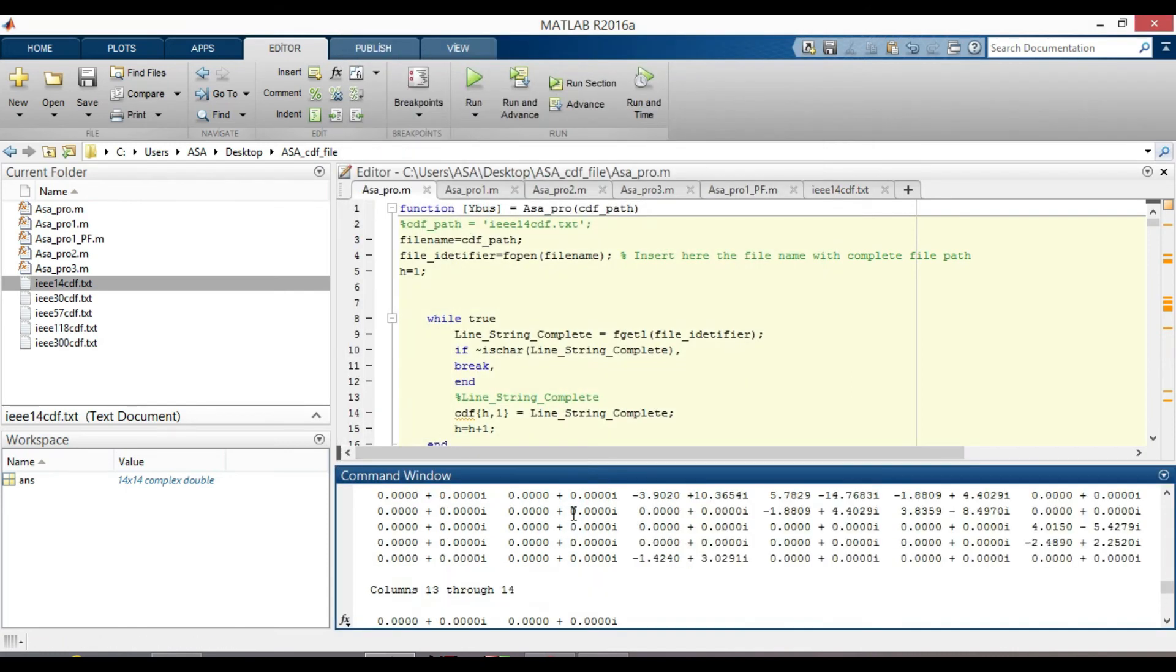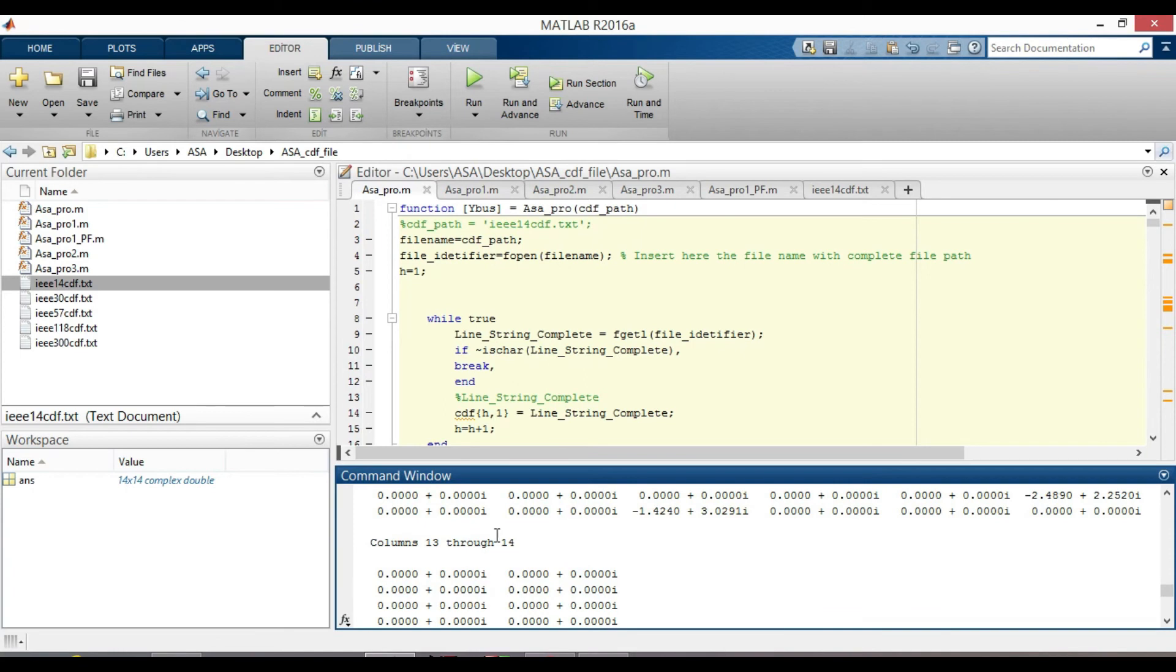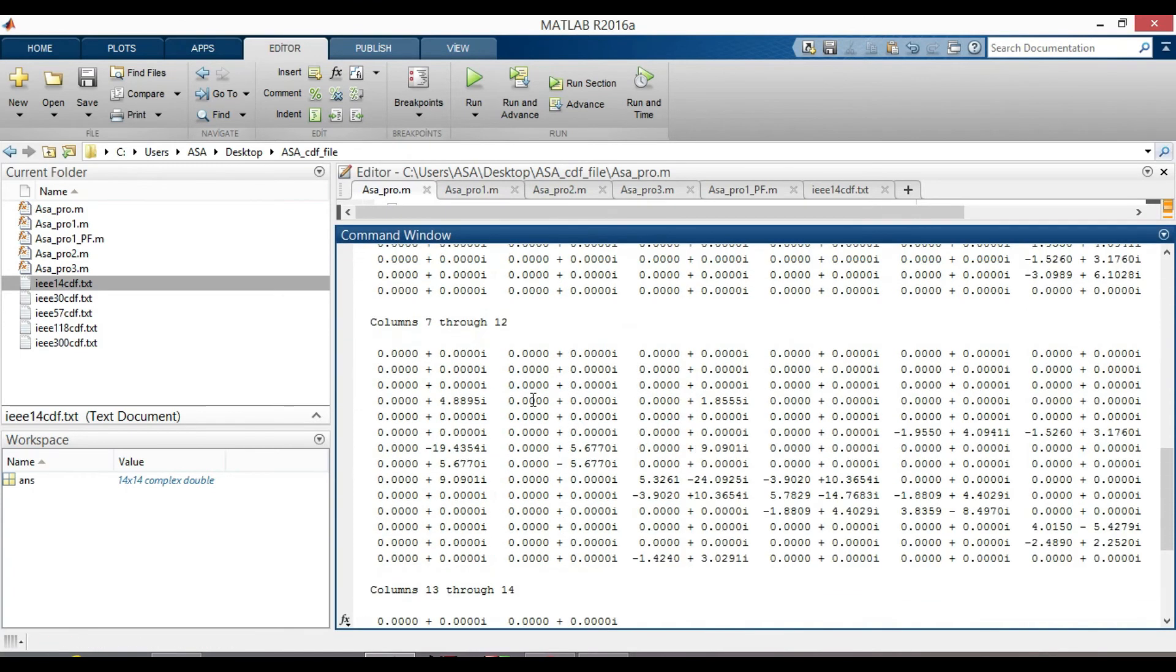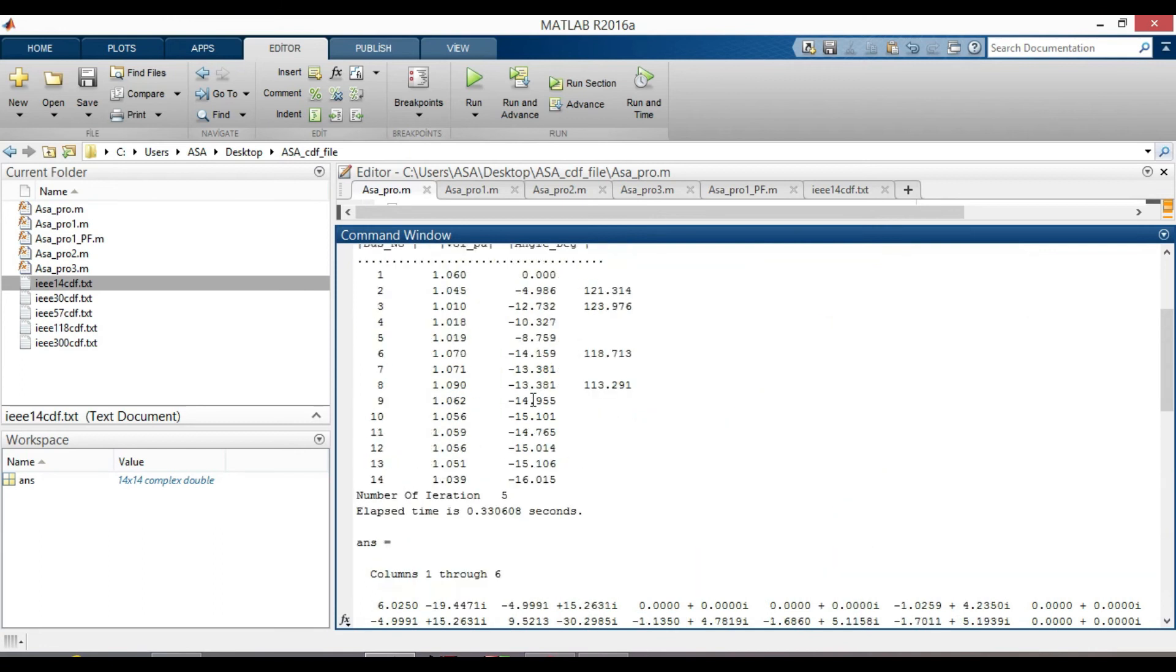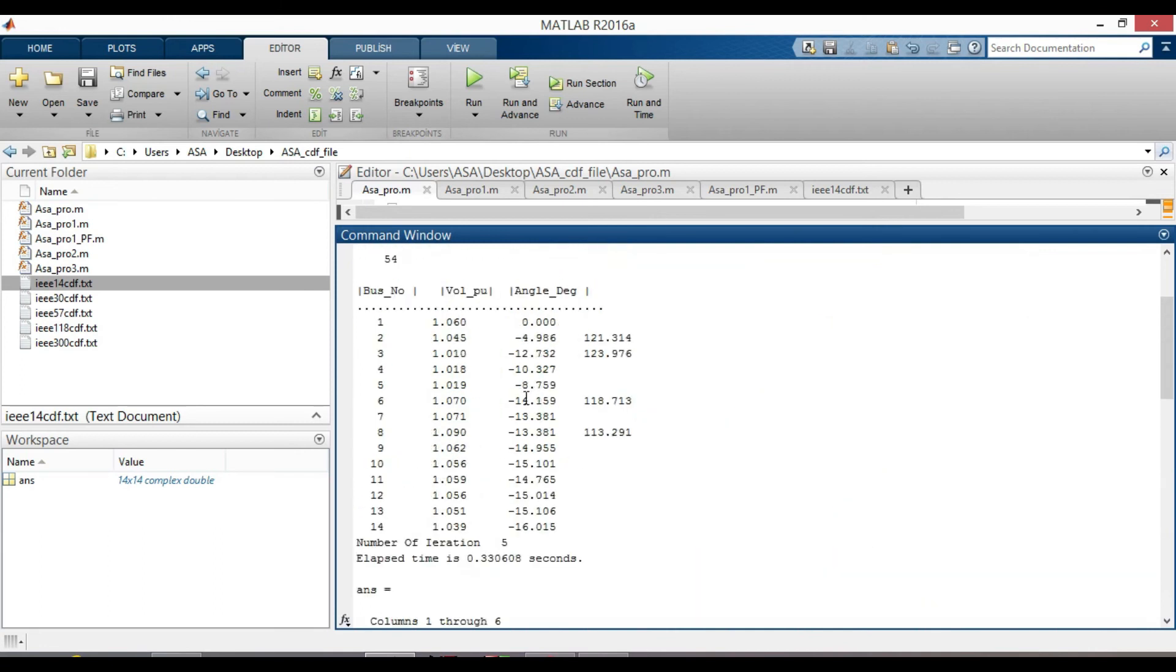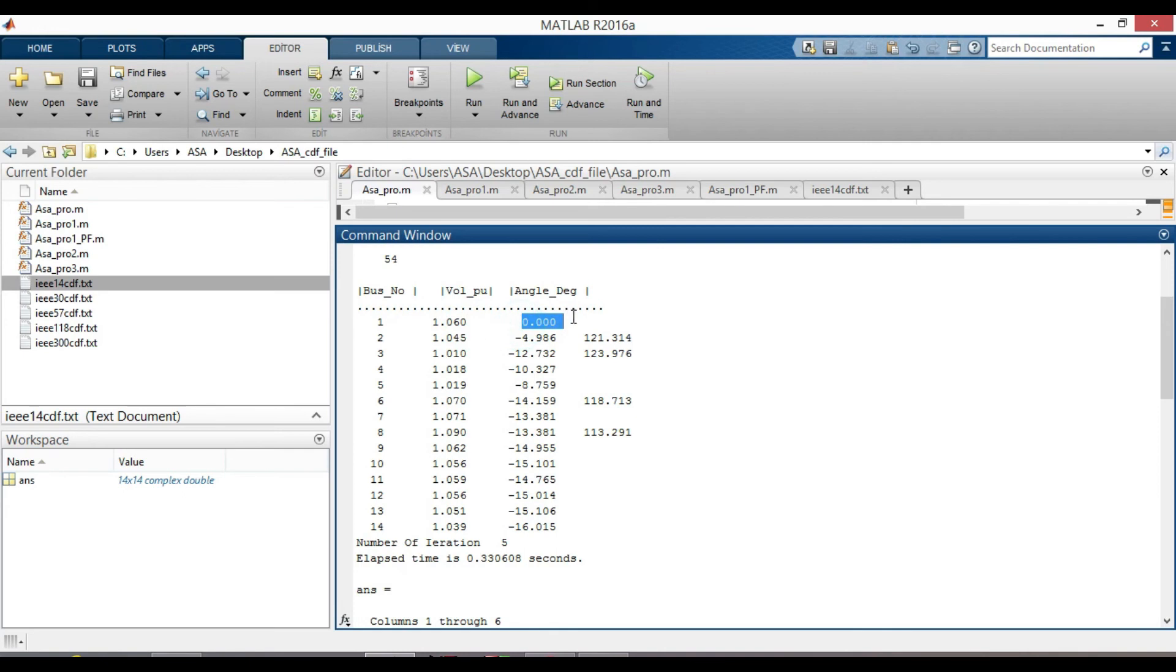If you look to the command window, you will notice the bus numbers start from bus 1 to 14. This column represents the magnitude voltage in per unit. And this one shows the angle in degree. Bus 1, as we explained earlier, represented the slack bus. That magnitude voltage is known and angle is 0.